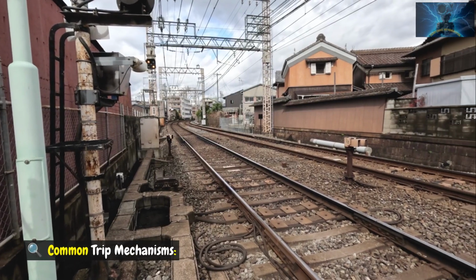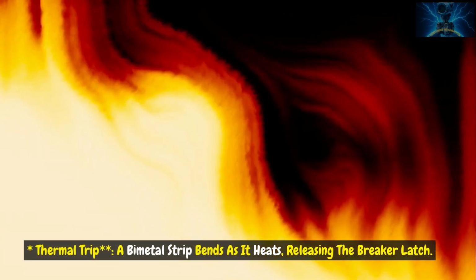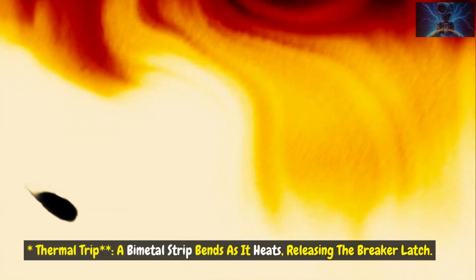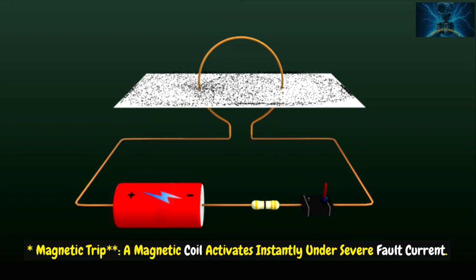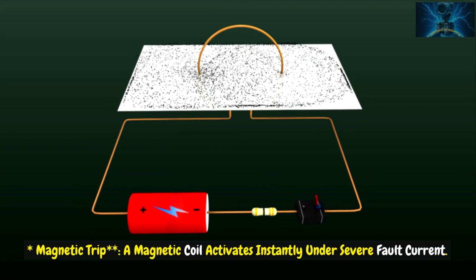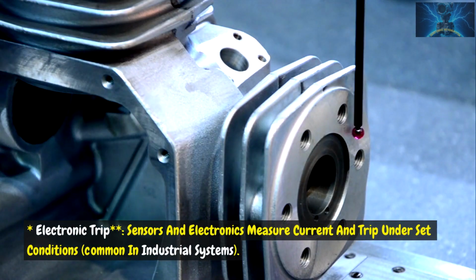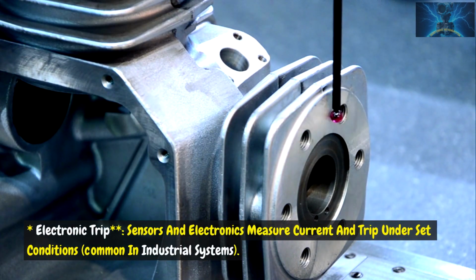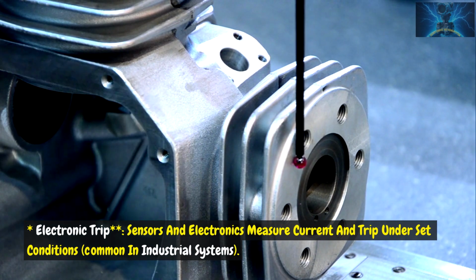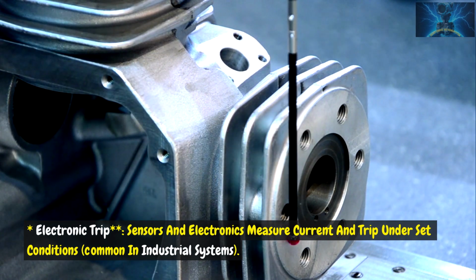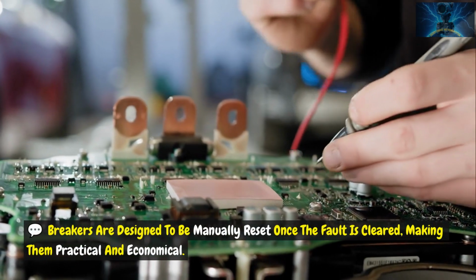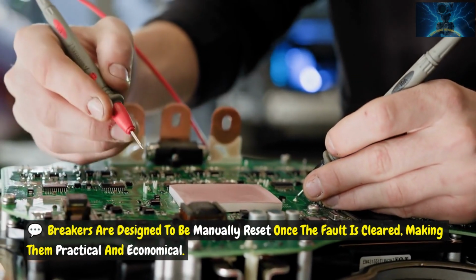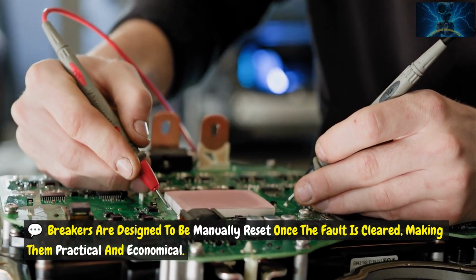Common trip mechanisms. Thermal trip. A bimetal strip bends as it heats, releasing the breaker latch. Magnetic trip. A magnetic coil activates instantly under severe fault current. Electronic trip. Sensors and electronics measure current and trip under set conditions, common in industrial systems. Breakers are designed to be manually reset once the fault is cleared, making them practical and economical.